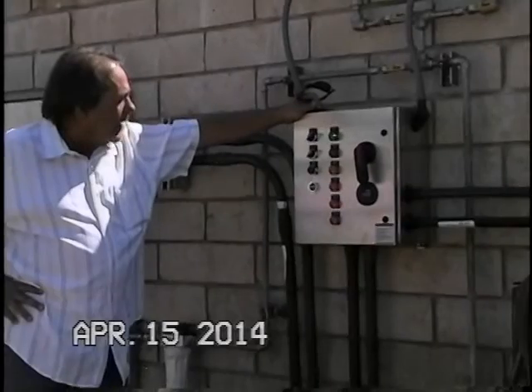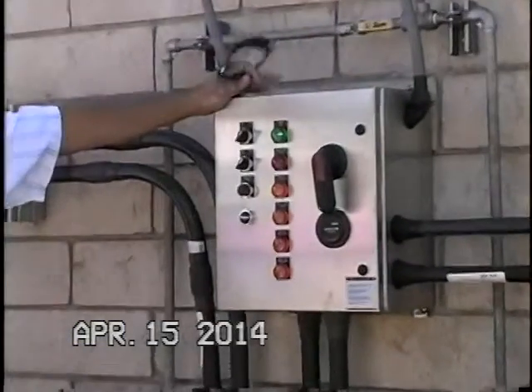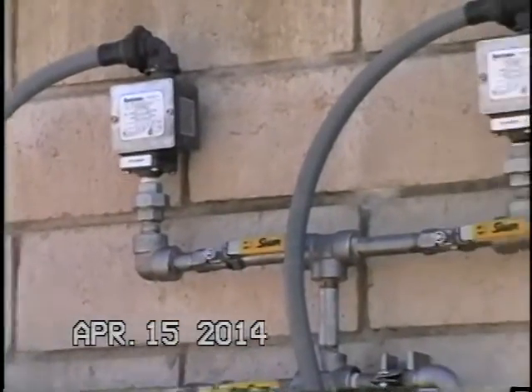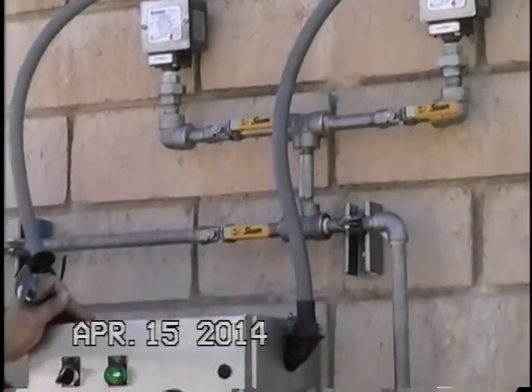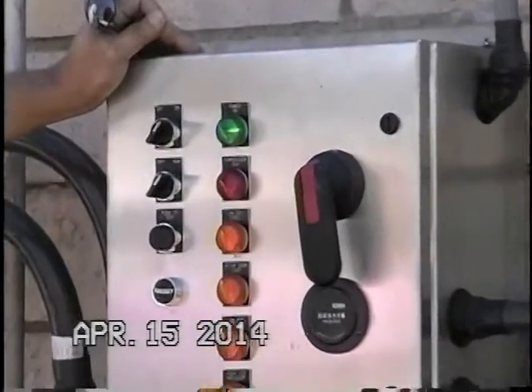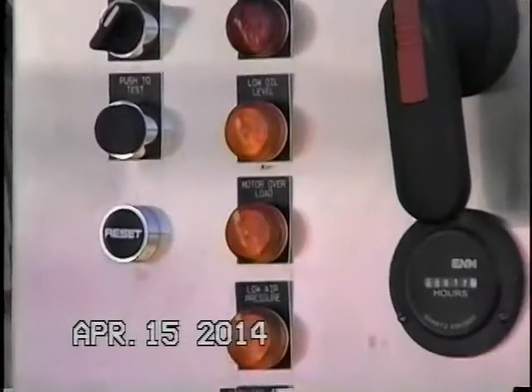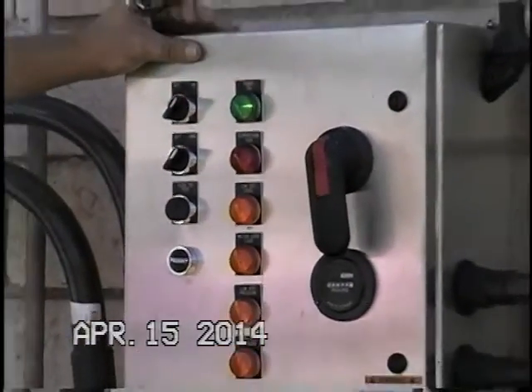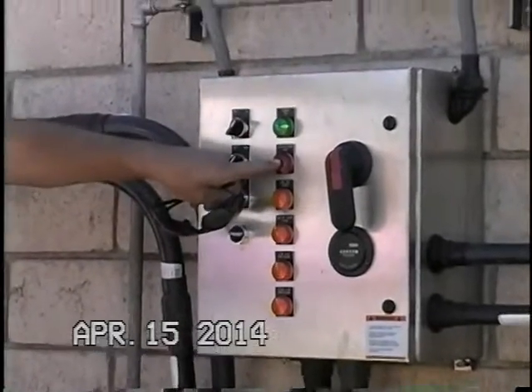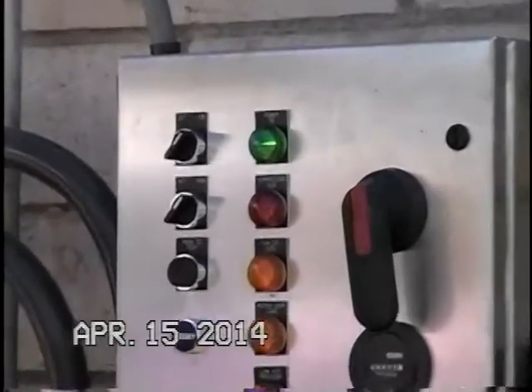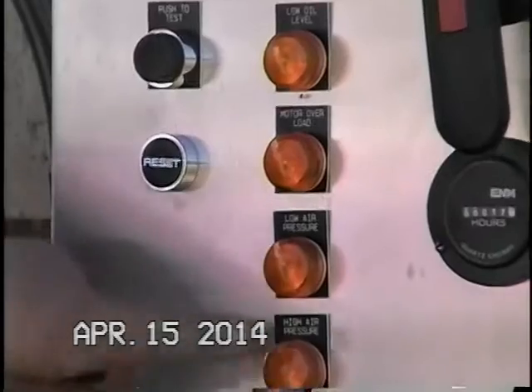You have a variety of alarms, same way on the compressed air system. You've got a high pressure alarm and a low pressure alarm. Those are set beyond the operating levels and below the operating levels on the low pressure switch. You also have a variety of alarms being monitored by the panel, then sent to SCADA. We have the compressor run, a function that's sent back to the SCADA system, so they'll be able to see whether it's running or not. Also low oil level, motor overload, and low and high pressure.